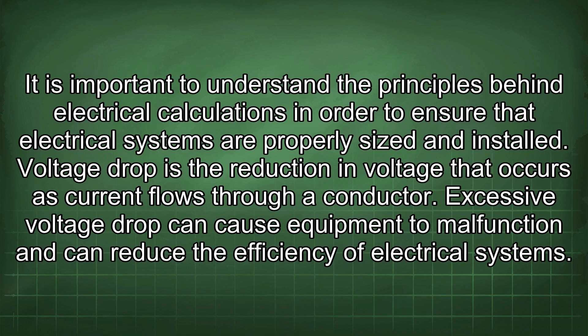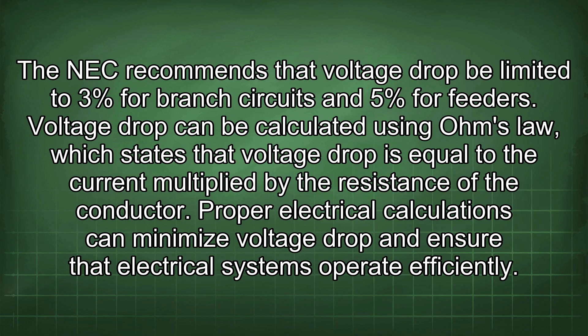The NEC recommends that voltage drop be limited to 3% for branch circuits and 5% for feeders. Voltage drop can be calculated using Ohm's law, which states that voltage drop is equal to the current multiplied by the resistance of the conductor. Proper electrical calculations can minimize voltage drop and ensure that electrical systems operate efficiently.